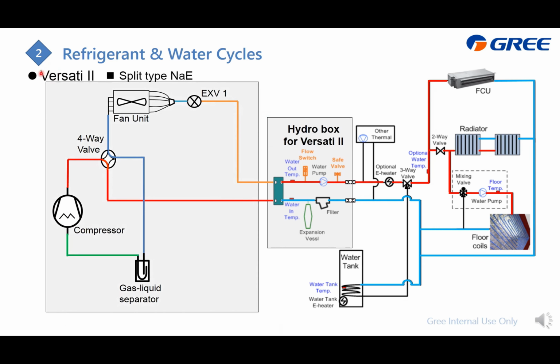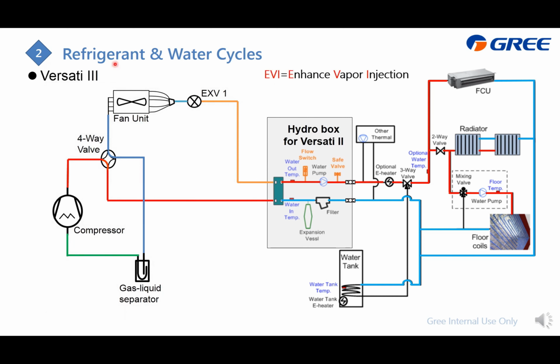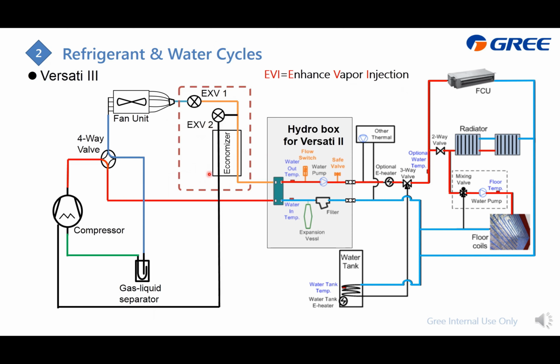And this part is what we call the VERSATI2 split type NAE series. And for VERSATI3, we adopt the EVI, short for Enhanced Vapor Injection, which means we need to make a change to this part, which is to introduce another plate heat exchanger and also another EXV. Also in heating, a partial refrigerant from this main row will get through this EXV2 and become low pressure and low temperature. Then it can absorb heat from the main row. Then it becomes gas and is injected into the compressor. This can raise the heating capacity and also the performance, especially in low temperature heating.